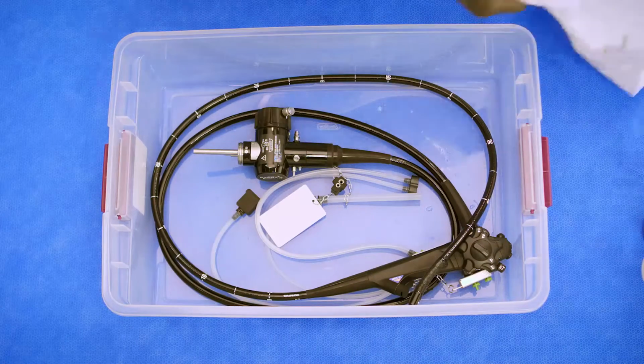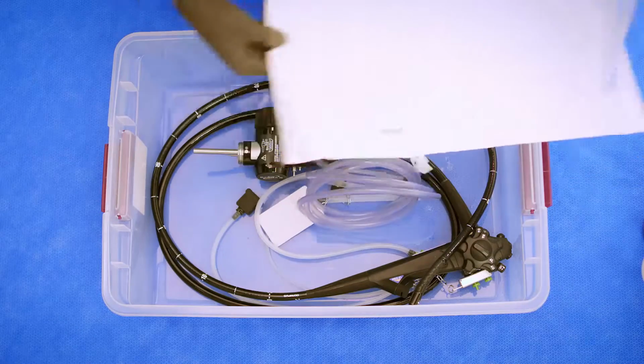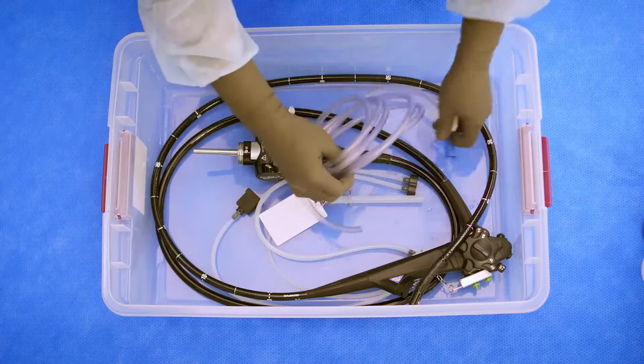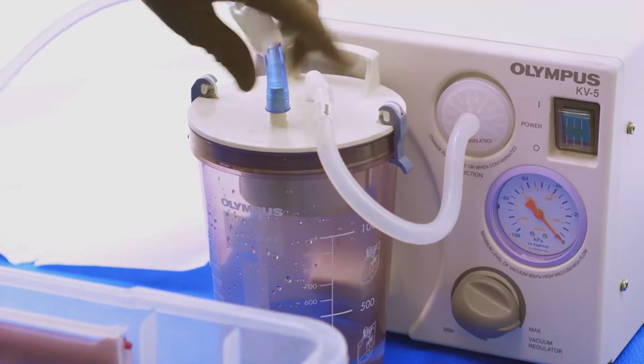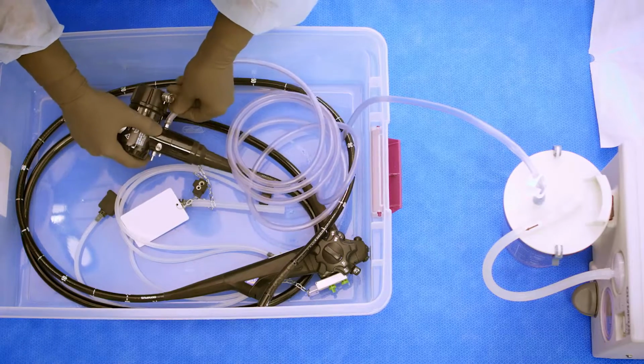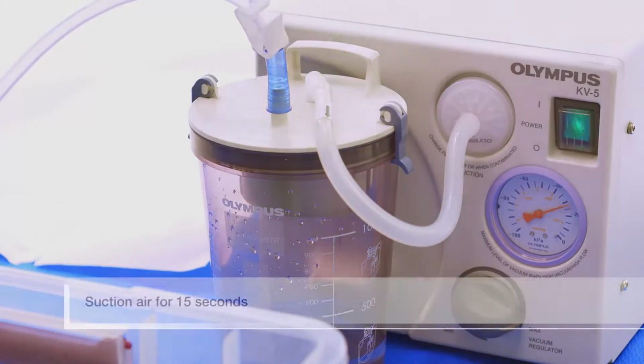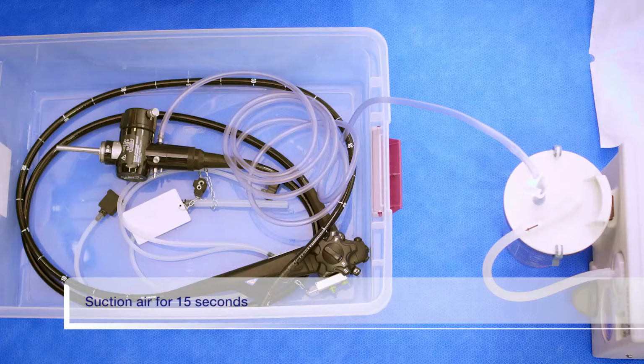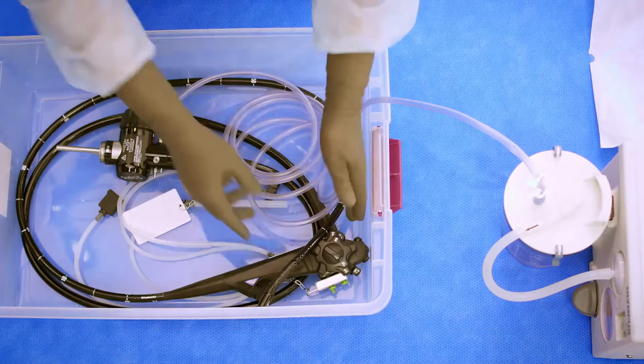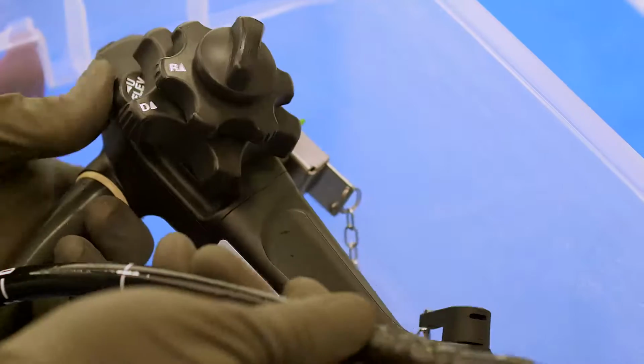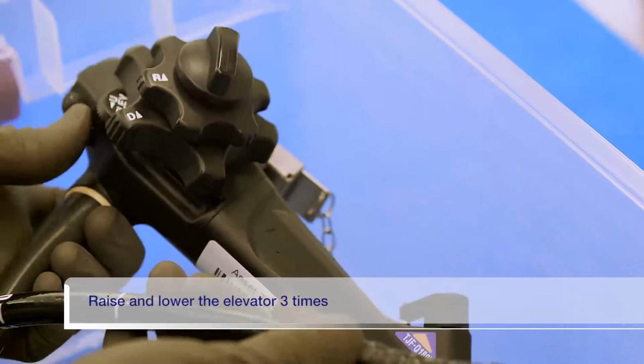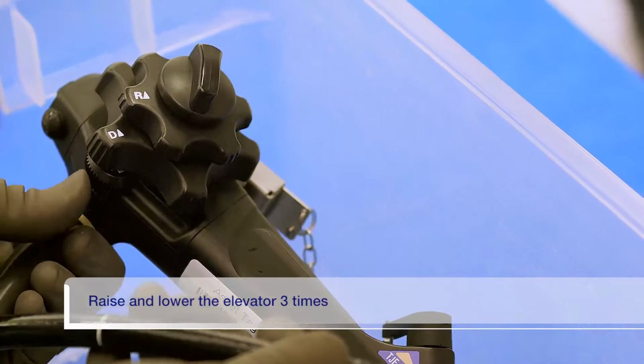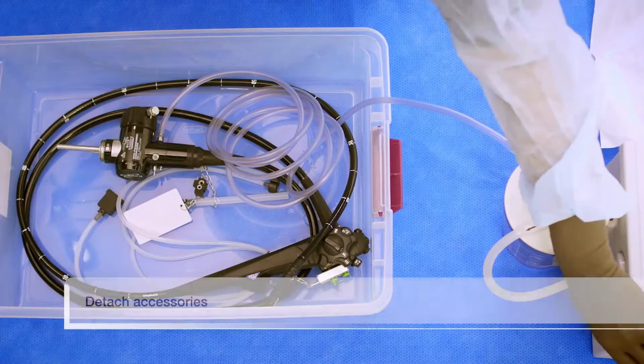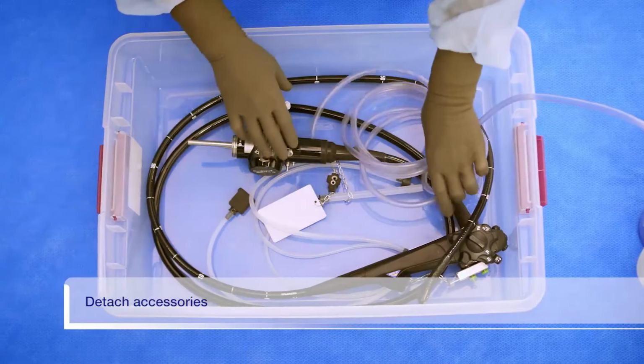Attach a sterile suction tube from the suction pump to the suction connector on the endoscope connector. Turn the suction pump on and aspirate air for at least 15 seconds. Air will flow through the instrument channel and the suction channel of the endoscope. While continuing the aspiration, raise and lower the forceps elevator 3 times by turning the elevator control lever. Turn the suction pump off and detach the suction tube and channel plug from the endoscope.